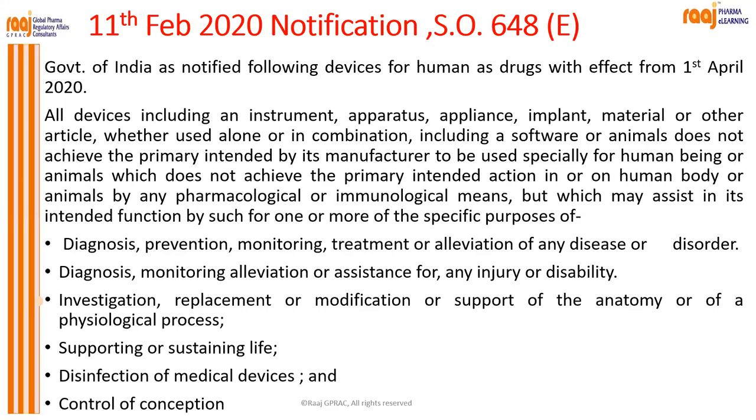So before, like Madam explained, there was a different authority for drugs, and they were planning on making a different authority for medical devices. But on 11th Feb 2020, they made a new notification that all of the medical devices will come under CDSCO itself. They felt that the organization was already very well developed, so they could handle medical devices as well.